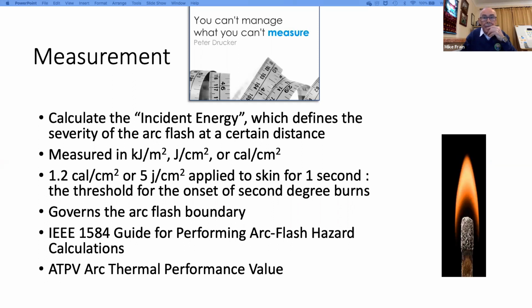So specifically, if we were to design PPE, the ATPV allows us to provide a measure by which the fabric will limit the amount of thermal heat on the outside, on the inside of the arc flash wear, down to 1.2 calories. So to try and explain that a little bit better, and I haven't there, but if you bought an 8-calorie boiler suit, for instance, if you had 8 calories of incident energy on the outside, that would attenuate that down to 1.2 calories at skin level.